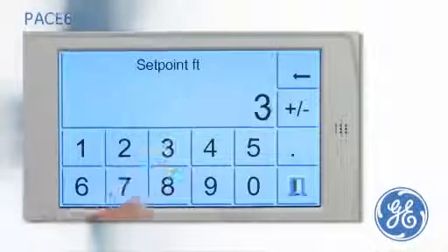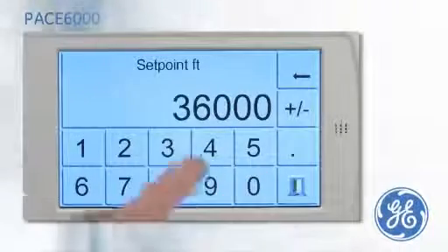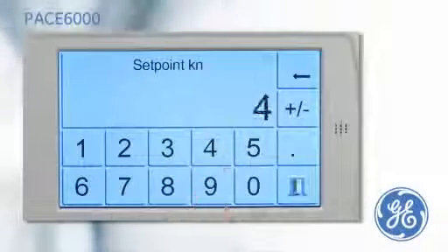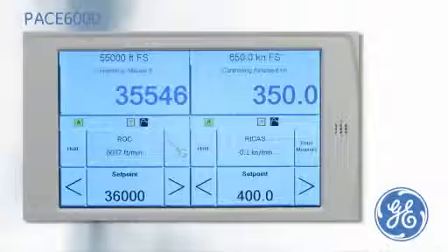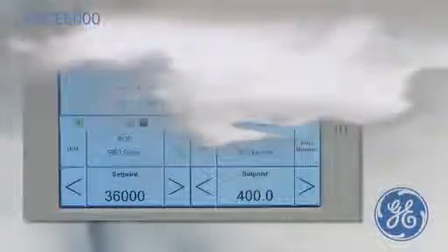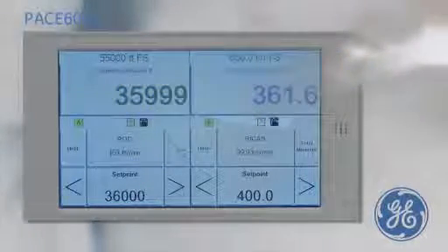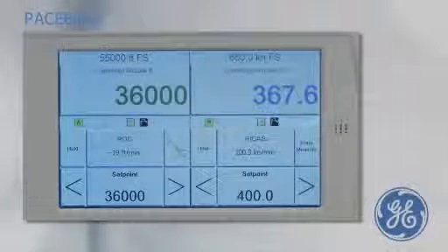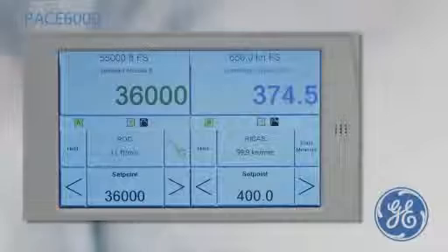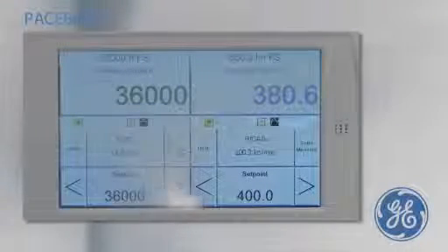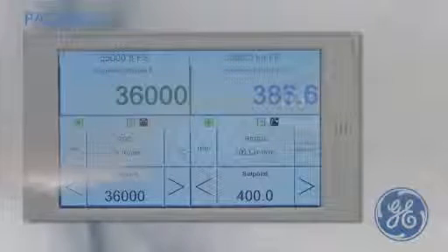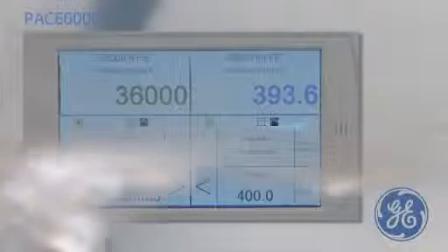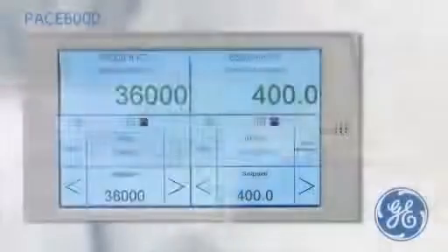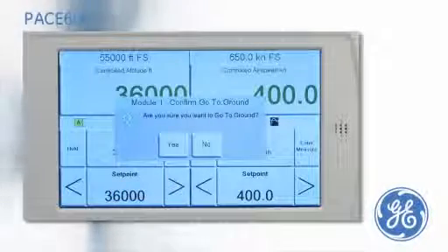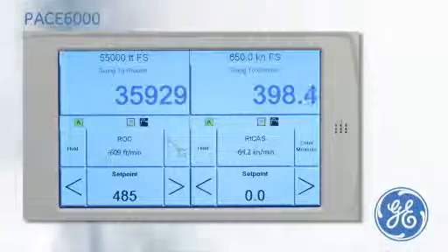A set point to simulate an altitude of 36,000 feet is entered. A set point to simulate an airspeed of 400 knots is entered. The PACE is now simulating a true airspeed relative to the altitude at the predefined rate of climb and rate of calibrated airspeed. When the go to ground button is touched, the altitude will decrease proportional to the airspeed at a controlled rate.